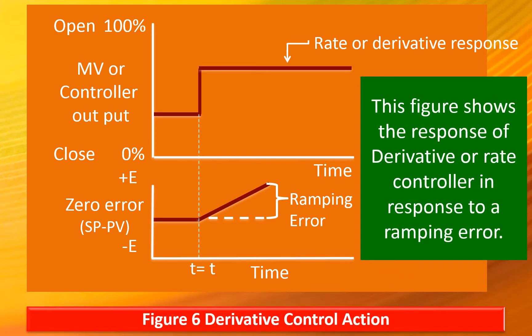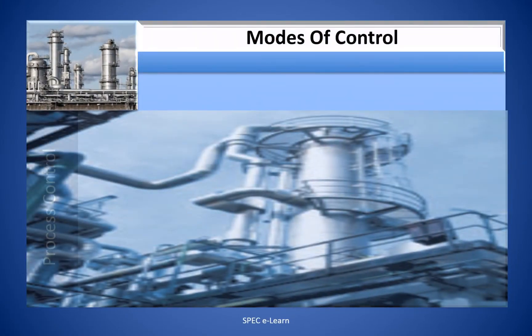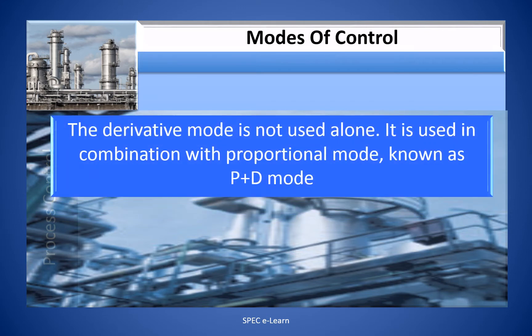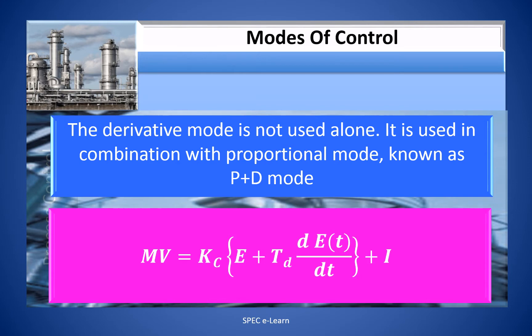This figure shows the response of a derivative or rate controller in response to a ramping error. Observe the derivative response alone — there is a step change in the controlled output when the rate of error change is detected. In real-world industrial practice, the derivative mode is not used alone; it is used in combination with proportional mode, known as PD mode. The MV in a PD mode is expressed as: MV = Kc × [e + Td × (dE/dt)] + i.